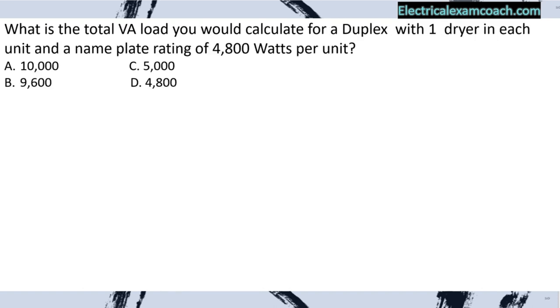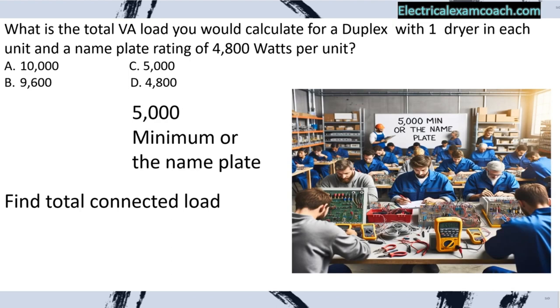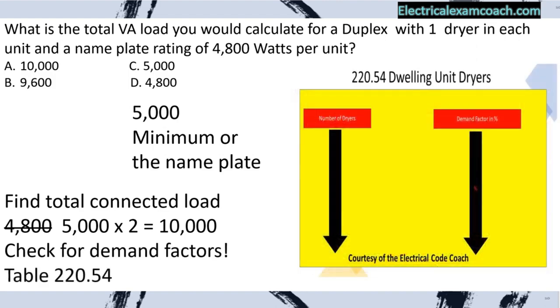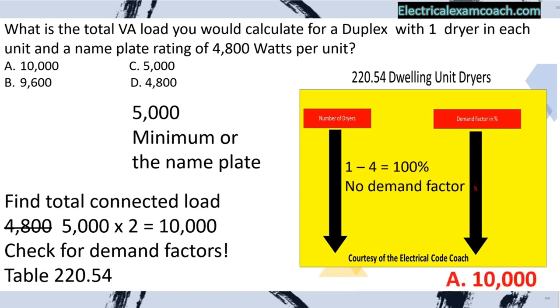Practice problem: What is the total VA load for one duplex with one dryer in each unit and a nameplate rating of 4,800 watts per unit? Find the total connected load: 5,000 minimum or the nameplate — the 4,800 is replaced by 5,000. Multiply by two units: 10,000. Check for demand factors: Table 220.54 shows one through four dryers at 100%. We select A.